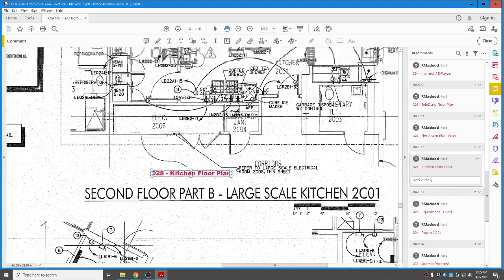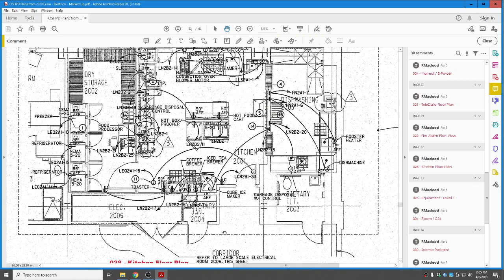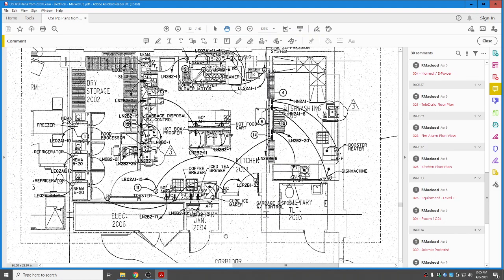Shown here is the large-scale electrical plan, page E 6.01. A lot of the equipment that we saw in that kitchen legend, you'll find here. Let's start on the left side. You'll see the freezer with a receptacle, wall supported, 86 inches above the floor. Refrigerator, 86 inches above the floor for that receptacle again. Same thing with the one down below. It shows you the panel and circuit that will be providing power to those receptacles, and as you can see, they're dedicated. This one refrigerator, circuit 14, the other refrigerator, circuit 12, the other freezer, circuit 10, all on the same equipment branch panel.